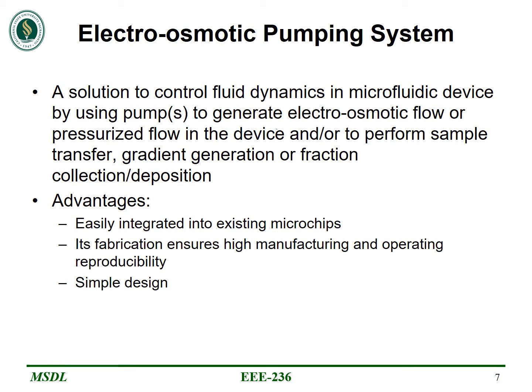Coming to the important component of the microfluidic device that we didn't discuss in the previous slides, the electro-osmotic pumping system. It is a solution to control fluid dynamics in a microfluidic device by using pumps to channel electro-osmotic flow or pressurized flow in the device to perform sample transfer, gradient generation, fraction collection or fraction deposition.